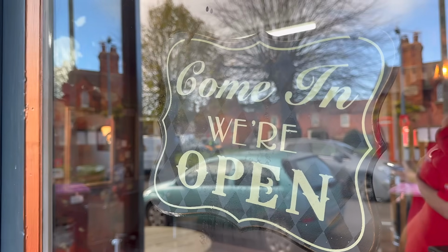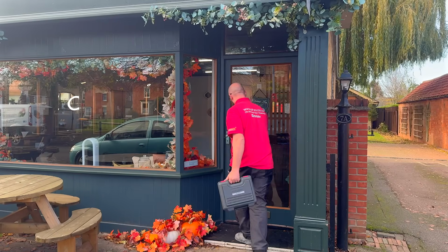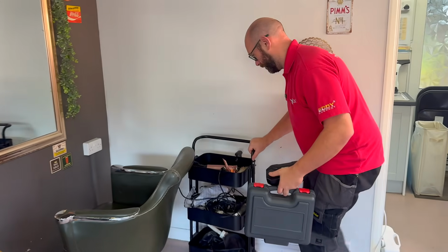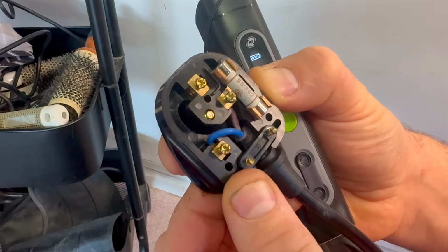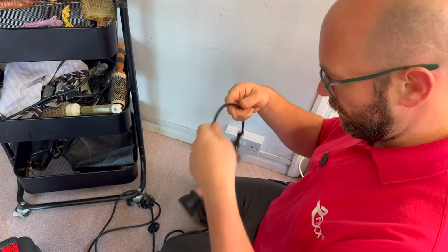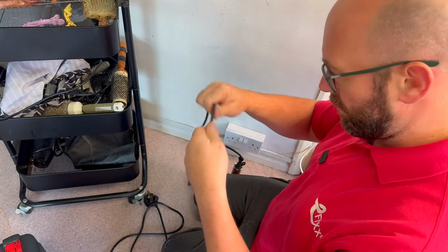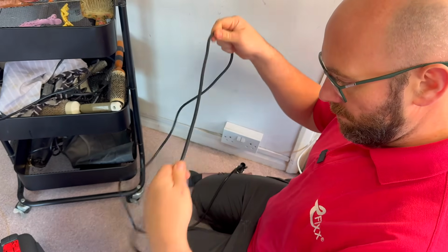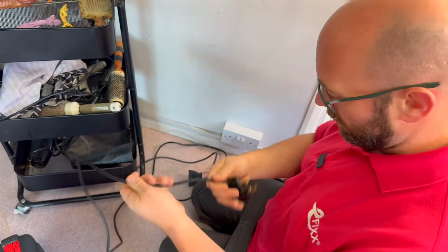I recently visited my local hairdresser and offered to PAT test their appliances for some special hair tonic. And we start with this hairdryer. The symbol is class 2, the fuse is fine, and the casing and lead all look in good condition. This is a handheld appliance, so I do need to give it a good check over to make sure there's no hairline cracks or deterioration in insulation anywhere.